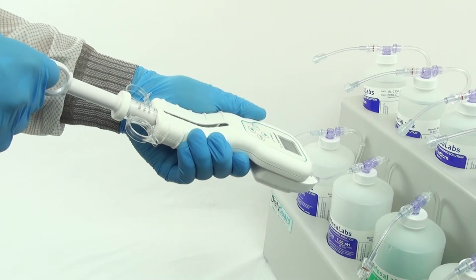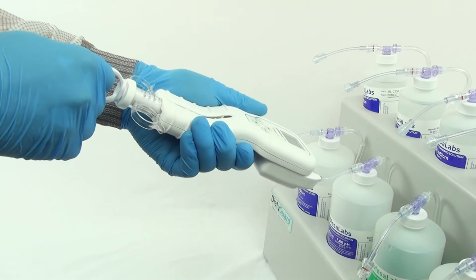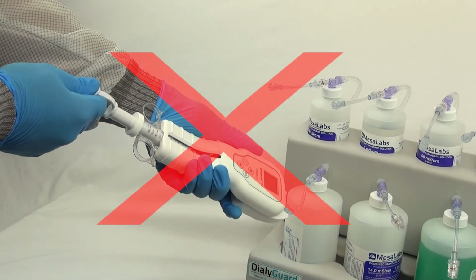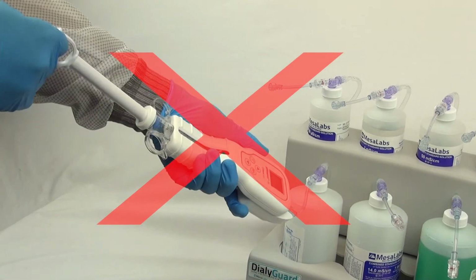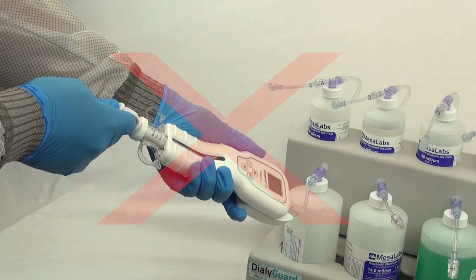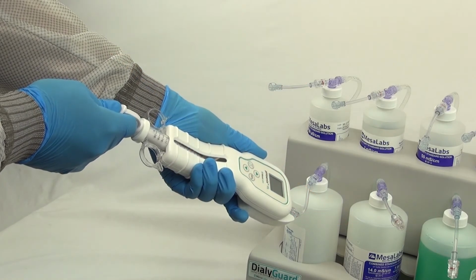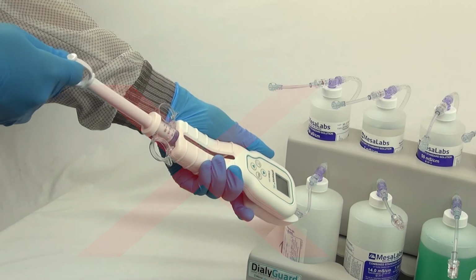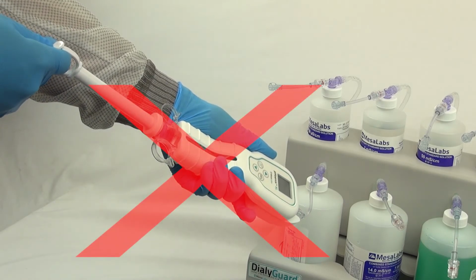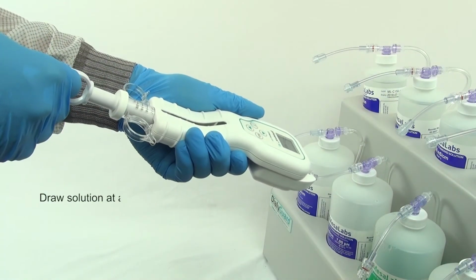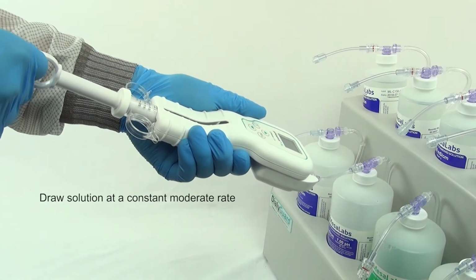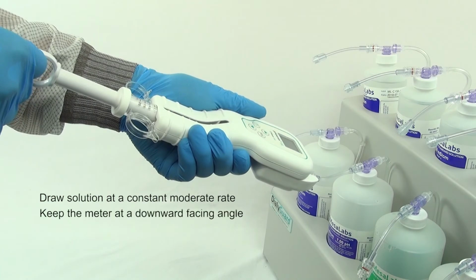After you have flushed the meter with the solution, start your calibration by pulling the syringe at a constant, moderate rate. Make sure that you don't draw solution in too quickly or too slowly. Otherwise, it will be difficult to reach a stable reading, and you may consume more solution than necessary. It's also important to remember not to draw the syringe plunger all the way. This may result in the syringe leaking and uses excessive solution volume. Draw solution at a constant, moderate rate, making sure the meter is at a downward facing angle.